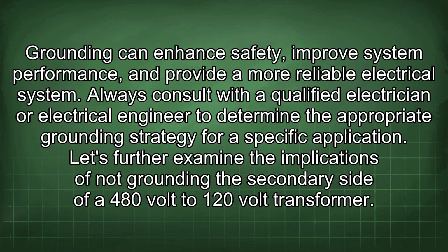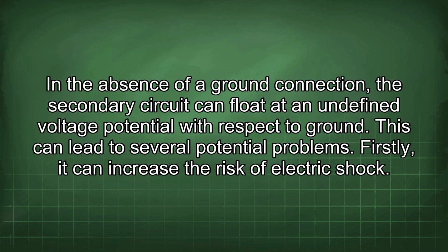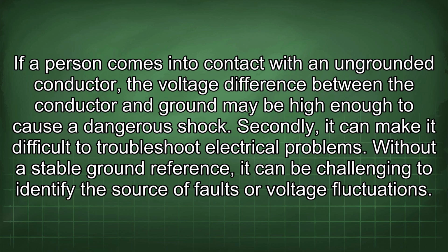Let's further examine the implications of not grounding the secondary side of a 480-volt to 120-volt transformer. In the absence of a ground connection, the secondary circuit can float at an undefined voltage potential with respect to ground. This can lead to several potential problems. Firstly, it can increase the risk of electric shock. If a person comes into contact with an ungrounded conductor, the voltage difference between the conductor and ground may be high enough to cause a dangerous shock.